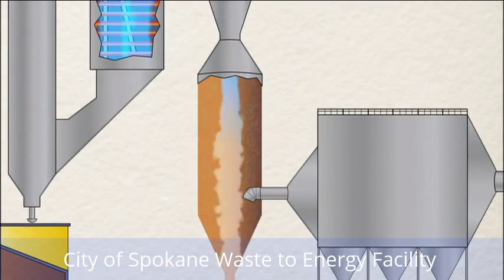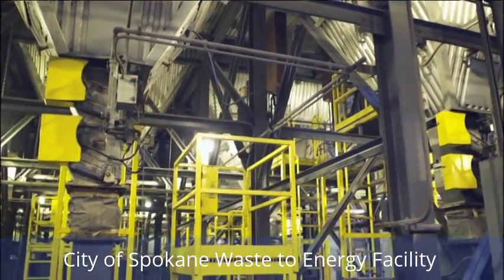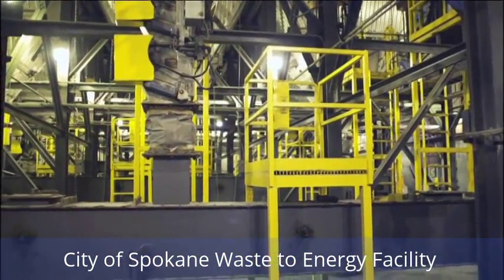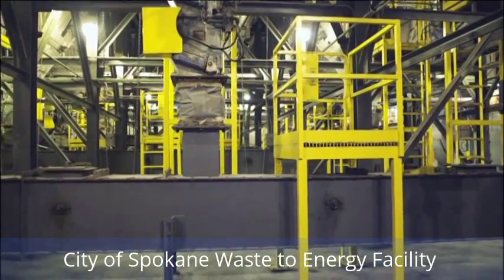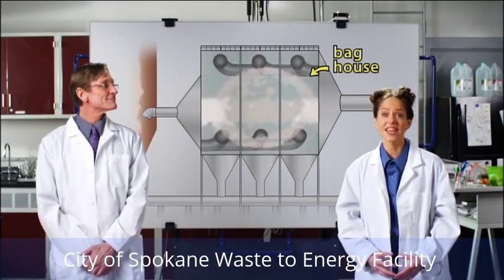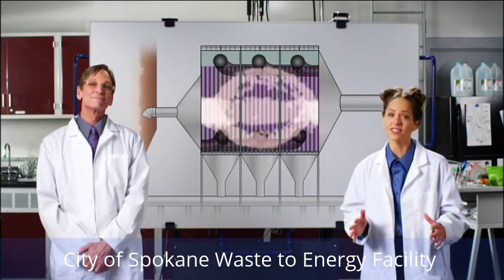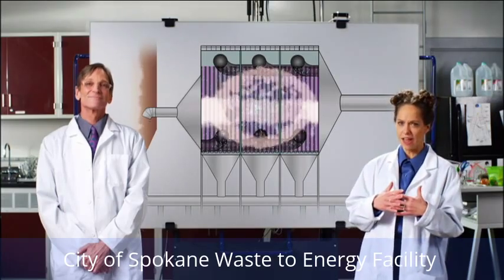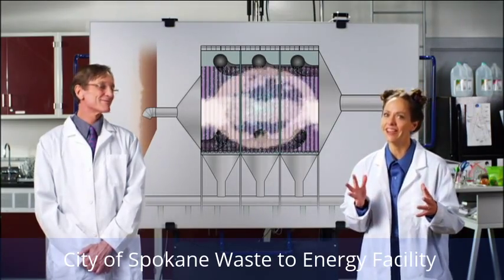As the gas cools, a dry powder forms. Then the freshly scrubbed gases go to the bag house, where they're cleaned even more. The gas contains very fine ash called fly ash, as well as powdered lime. The bag house works like a vacuum cleaner, filtering the ash through more than 3,500 Gore-Tex bags. Those bags capture the fly ash, letting only the clean air out.